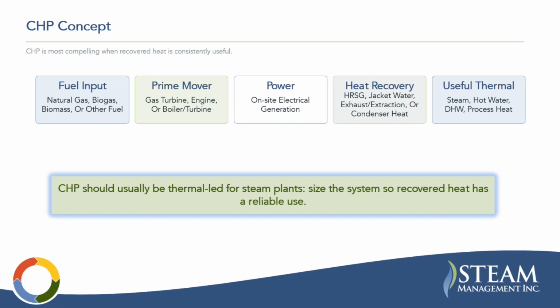Some major considerations are the fuel input. If you're generating steam and then using steam to generate power, you can use any fuels that are common in high pressure steam boilers. You want to consider your prime mover. That's your electricity generator generally. That could be a gas turbine, it could be a reciprocating engine, or it could be a steam turbine combined with a boiler, obviously. Power: what is the on-site power requirement and the benefit of on-site electrical generation generally? It could be avoiding interruption of production. What is the heat recovery method? And then what is the useful thermal energy potential?